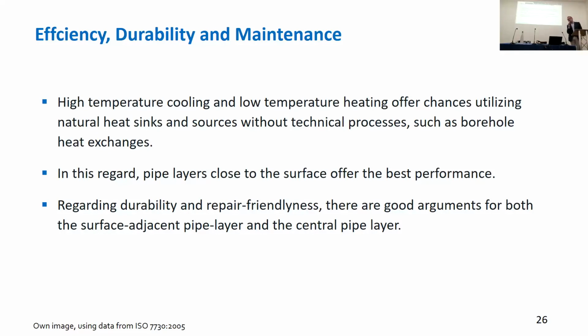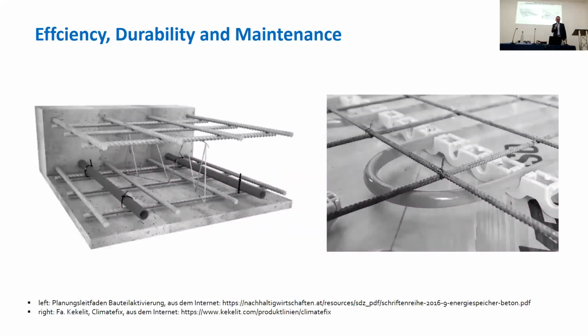In the area of cooling, we have a lot of systems which are only run by free cooling, so only via heat exchangers and not via chillers. And for sure, this is then energy efficient, but the system itself, the radiant surface, is not efficient or not efficient. We talk a lot about how to do them in construction, how to insert the pipes. There's this community which says, get it in between the steel of the ceiling, because there is the best place in thermal aspects to have the highest utilization of heat storage effects.